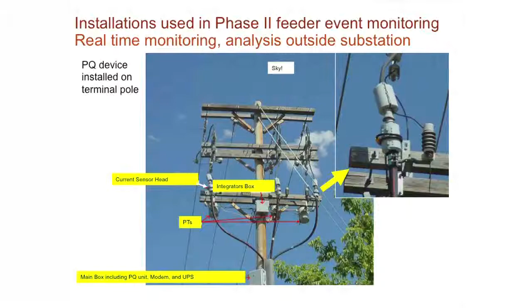Then we had some external installations. So it was those same power quality devices that we mounted on the terminal pole in this case, and we used Lindsay sensors, and then a rack of three-phase VTs, making secondary connections to the input of the power quality device. And then we had a remote connection back to the research folks, and they could retrieve data from it. This was located, let's say, halfway down the main line, so it was the overhead section and then went underground.